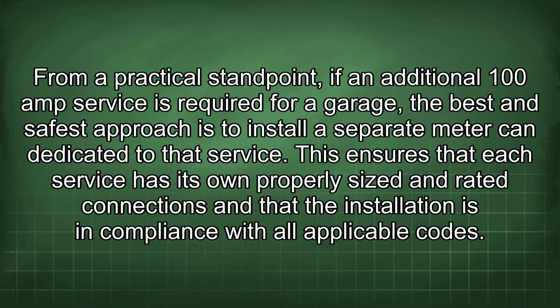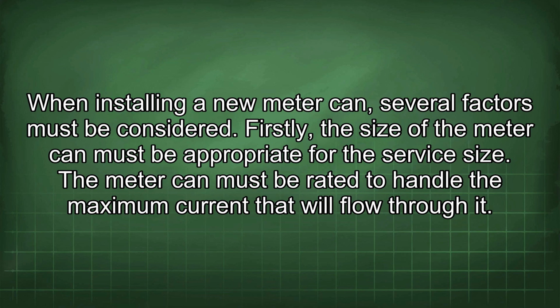From a practical standpoint, if an additional 100 amp service is required for a garage, the best and safest approach is to install a separate meter can dedicated to that service. This ensures that each service has its own properly sized and rated connections and that the installation is in compliance with all applicable codes. When installing a new meter can, several factors must be considered.